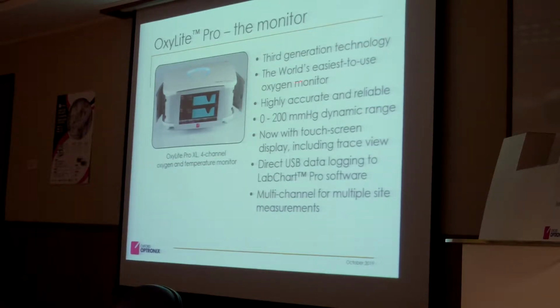The OxyLite is our third generation now, over the last 20 years. It's the easiest to use monitor because you have pre-calibrated sensors. You just plug the sensor in, it has the calibration data stored. There's no calibration necessary. Originally it was developed in a cancer lab, so it was important to get a very good resolution at the low oxygen readings. So it's very accurate there in the physiological range. The dynamic range goes up to 200 millimeter mercury, which is above the atmospheric oxygen we measure, that would be 159 millimeter mercury, so the range is sufficient.